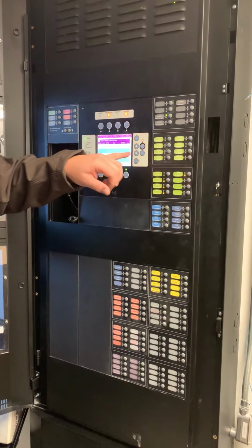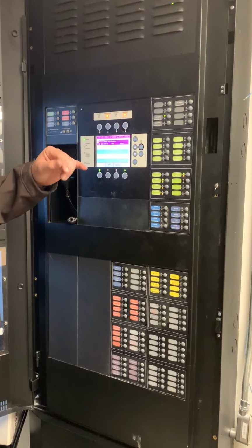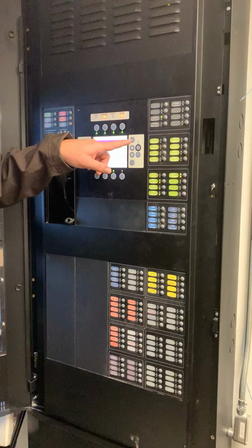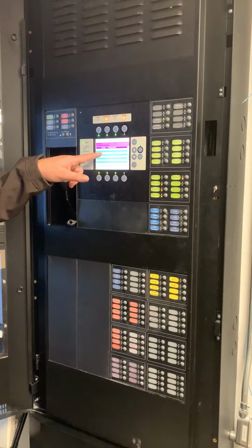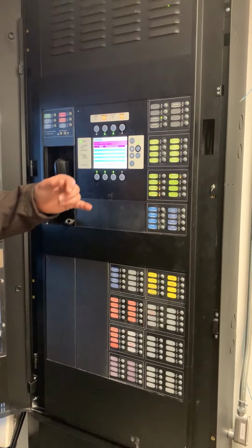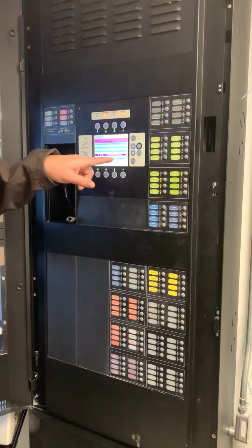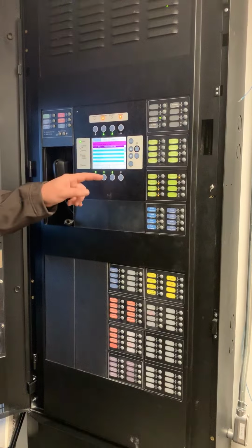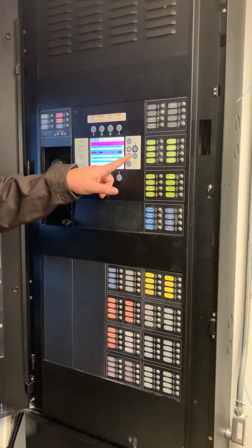if you go here, you get your address, 6th floor. I think that's node 3. So I would go here, go to menu, maintenance. This pops up. You get more info. I go to my 6th floor panel. I hit more info. You get your address, that loop number, we'll say it shows 6th floor detectors. We'll go to 6th floor, more info, and if you know the address, you can put in your address.